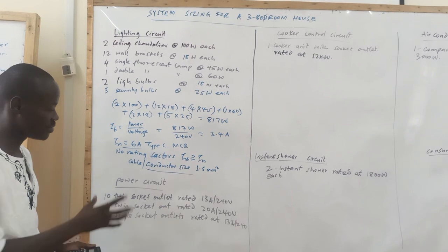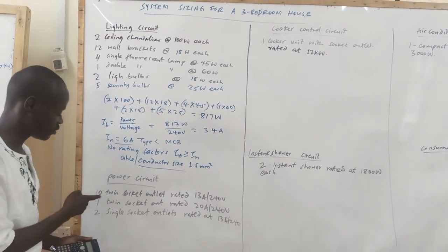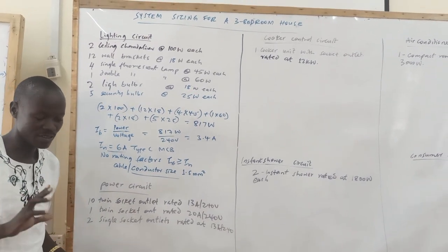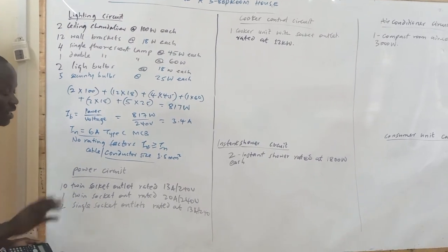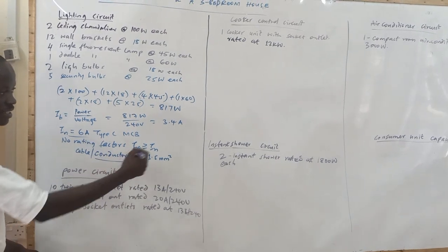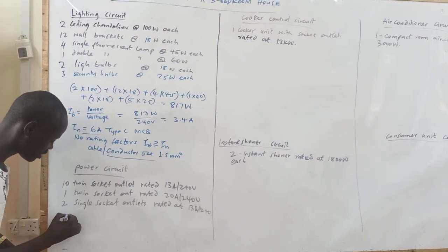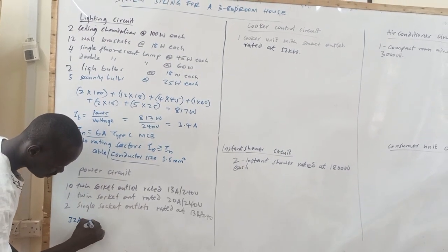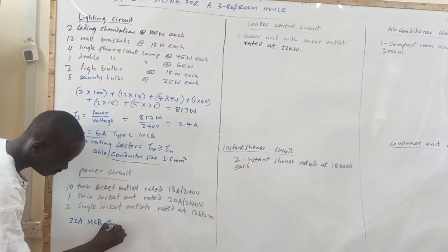But for the floor area that was given, and the fact that I'm also isolating one twin with this circuit, the floor area does not exceed 100 square meters for that building. So I'll be using a ring, and if I'm using this single core cable, it's recommended that I use a 32 ampere MCB, and this is type C.